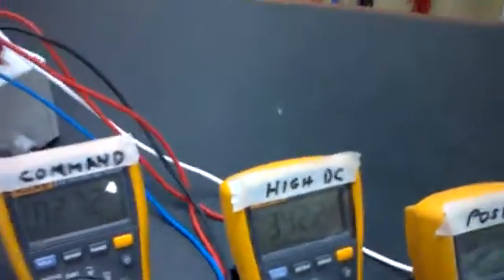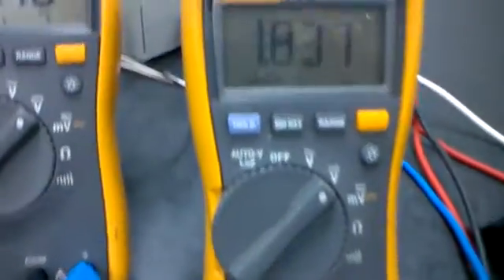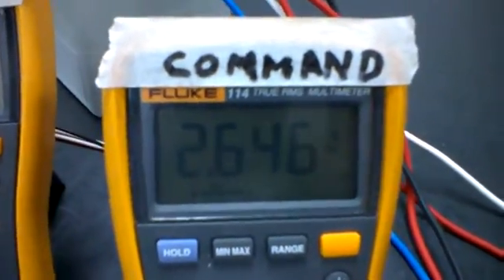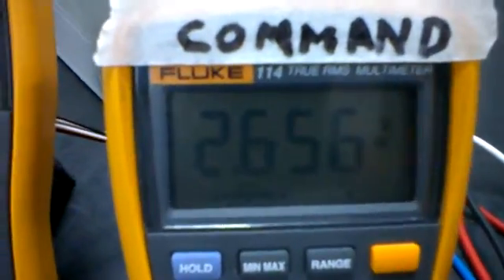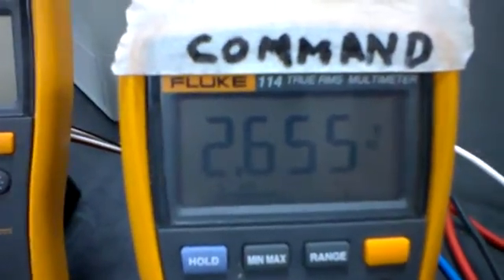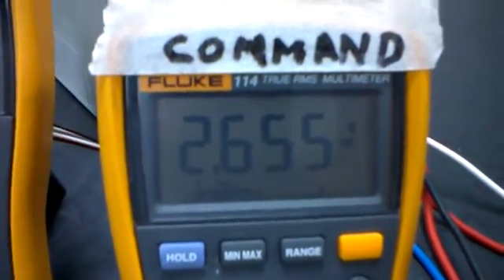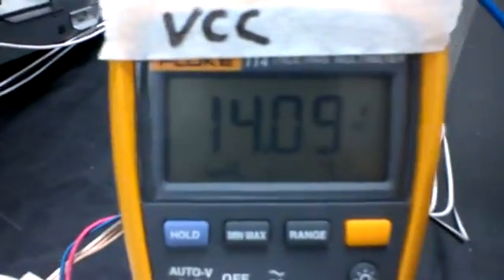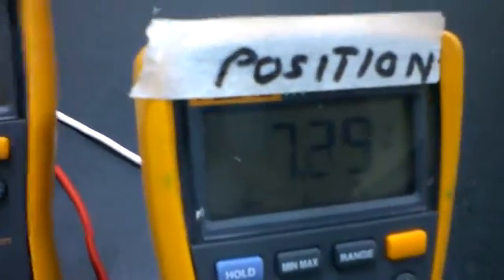Okay, now what I'm going to do is turn the motor on, and I've got it on a low speed at the moment, so I'll just turn it on. And what we should see shortly is, we'll see now that we've got a command voltage of about 2.6 volts. And this voltage is what the PCB is sending out to allow the motor to run. If we look back here, we've still got a stable control voltage. Our high DC has remained unchanged.